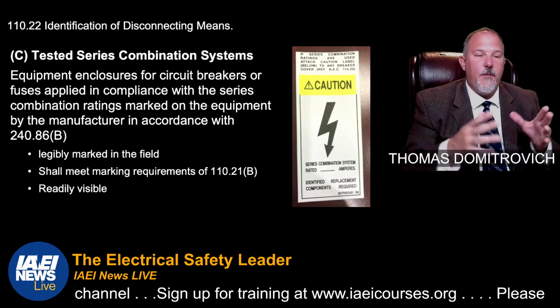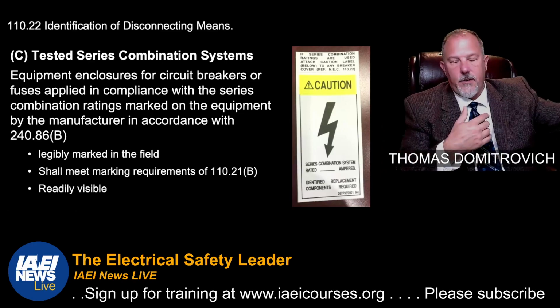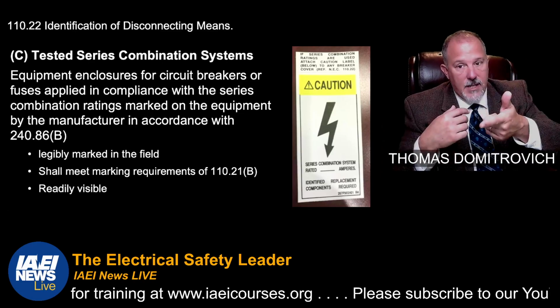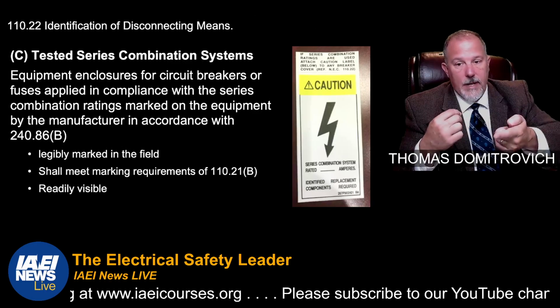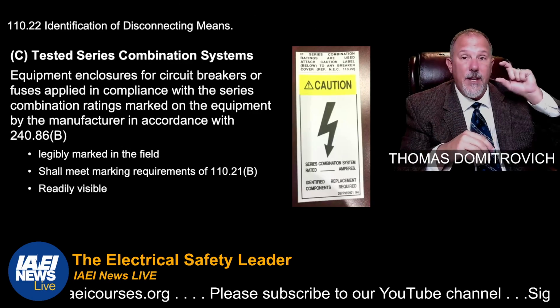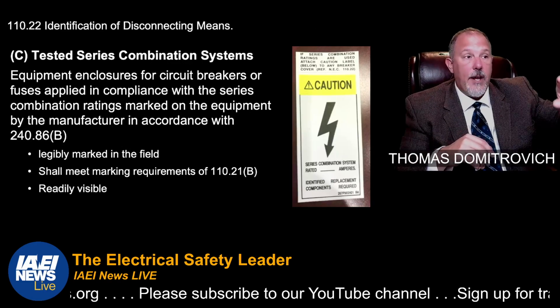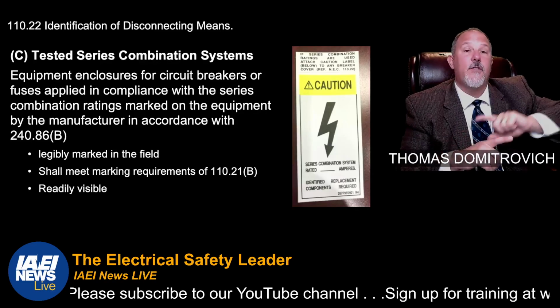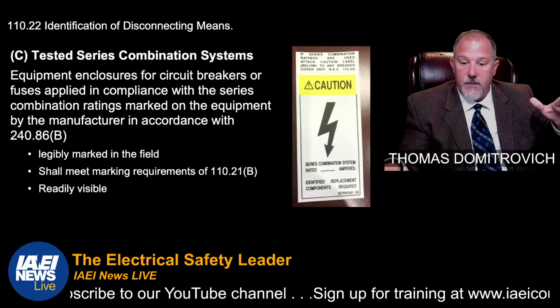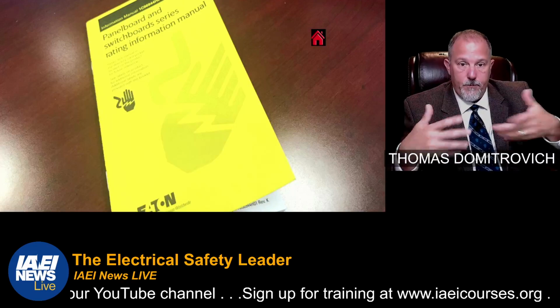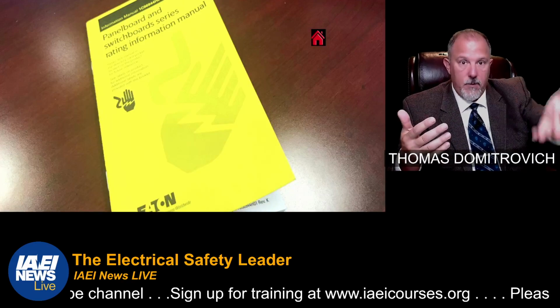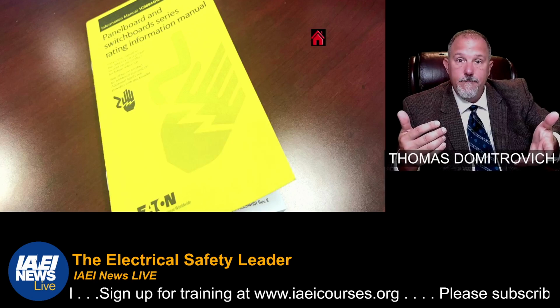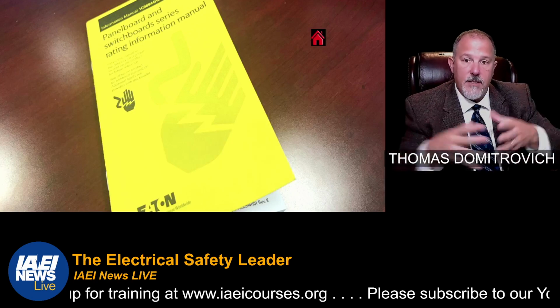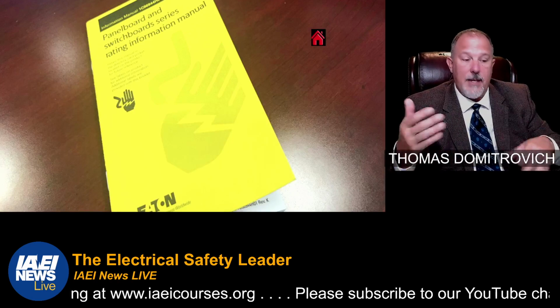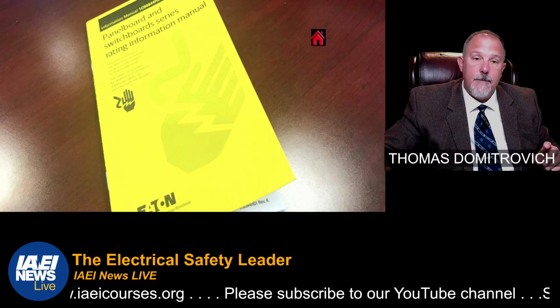And what I'm telling you, if you're working on a panel board and you're replacing overcurrent devices and you see these signs, series combination system, and what the rating of the amps is, make sure that you get the exact catalog numbers. And if you can't find the exact catalog numbers, you're going to have to go back to the tables, these books that we'll publish, and find out which ones work. Because you may have to re-series rate that system if you can't get that specific breaker or fuse. All right.